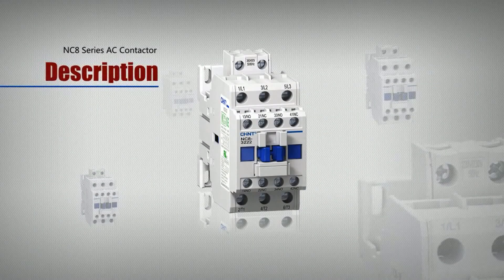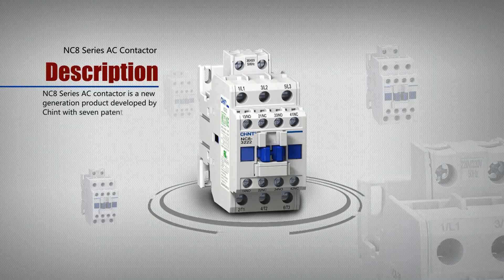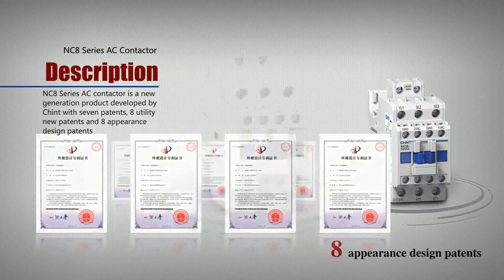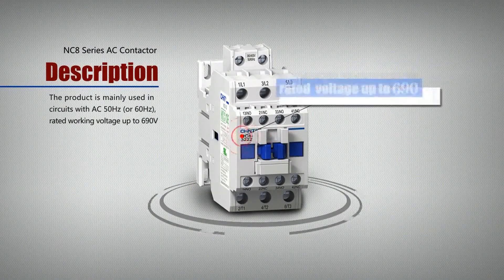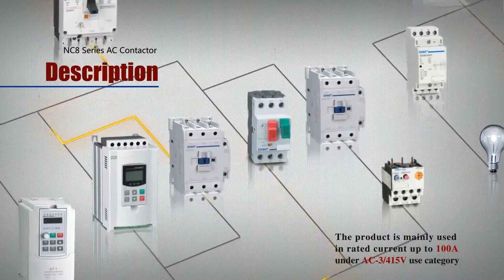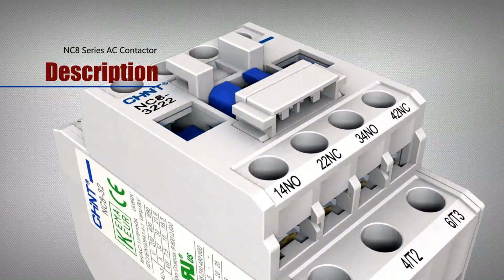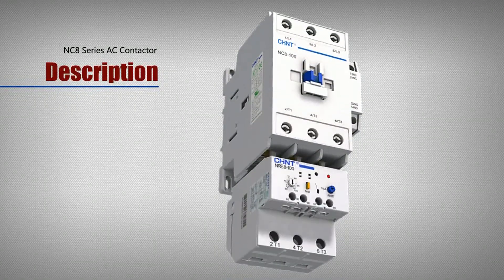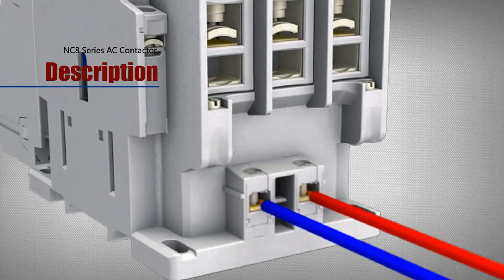NC8 Series AC Contactor is a new generation product developed by Chint with several patents, including 8 utility new patents and 8 appearance design patents. The product is mainly used in circuits with AC 50Hz or 60Hz, rated working voltage up to 690V and rated current up to 100A under AC3, 415V use category. It is used for long-distance connection and braking circuits, and combines with the appropriate thermal overload relay to be an electromagnetic starter for the protection of circuits with operation overload. The contactor is suitable to frequently start and control AC motors.